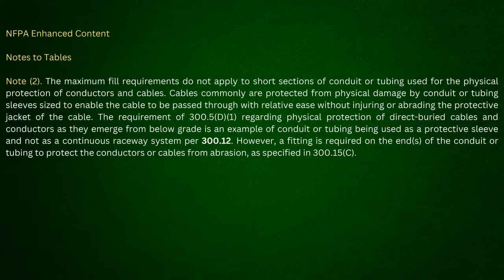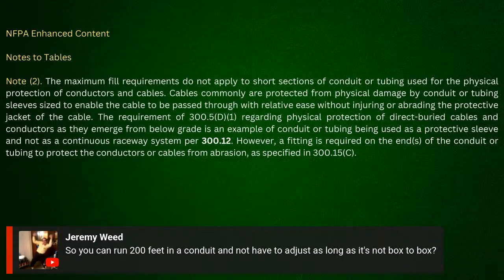And let's see what he's asking here. He said that's just for fill. Let's see what he's got here. So you can run 200 feet in a conduit and not have to adjust as long as... Now, see, this is what you get into when you get stuff like this. They give you something that nobody is going to put 200 foot of conduit in as a sleeve. This is where it gets ridiculous. A sleeve is to protect from physical damage. That's it. It ain't used for anything else. And for you to give these hypotheticals, why would you run a 200 foot sleeve?